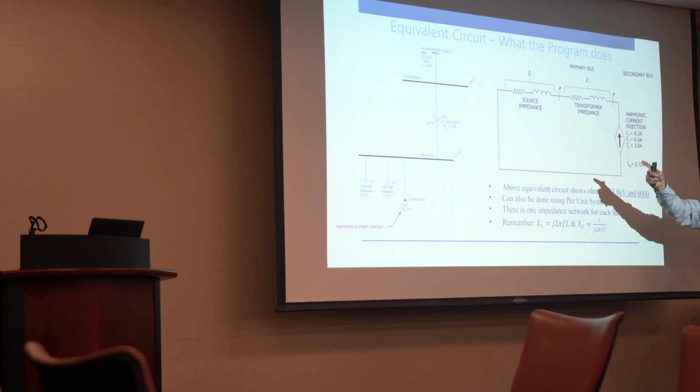You can do this very easily within any analysis program and do just a simple current injection, even if it's 1 amp at every frequency. Do your analysis and ask, does it make sense what I'm getting? That's the purpose of this: to allow you to go back to your program and understand what it's doing.